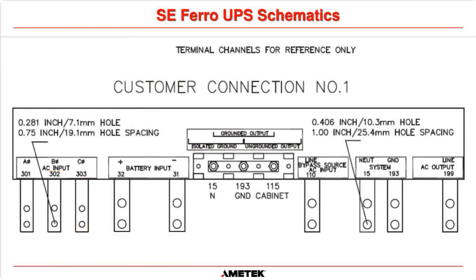If you connect this reverse polarity, and everybody will say, oh, we would never do a thing like that. You have no idea how many times people connect a battery to our system reverse polarity, don't check it, then they close the battery input breaker and they damage the system. Okay, and we're not going to come out and replace that under warranty. If you do that, and we'll know that you've done it, because there's some things in there to try and protect serious damage from happening, but we'll know that you've done it, and unfortunately we'll have to charge to come out and fix that. So don't do it, and therefore we won't have to come out and fix it for you. The next, so that is the AC input, that's the battery input.